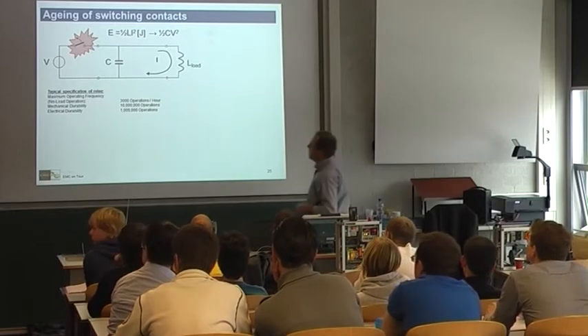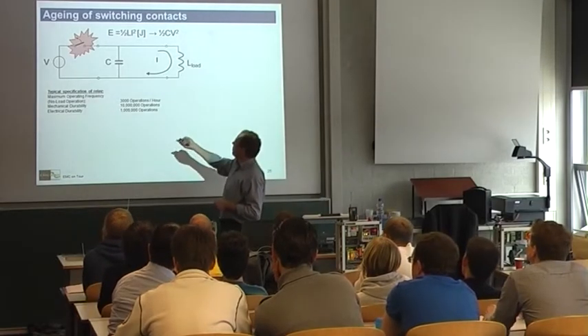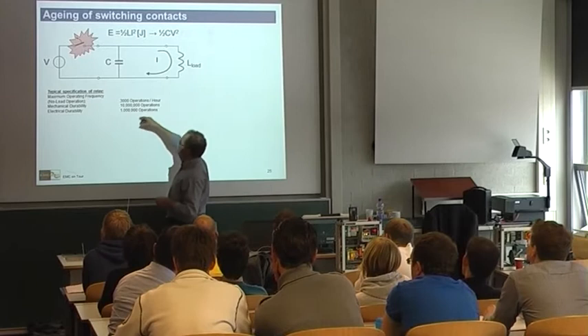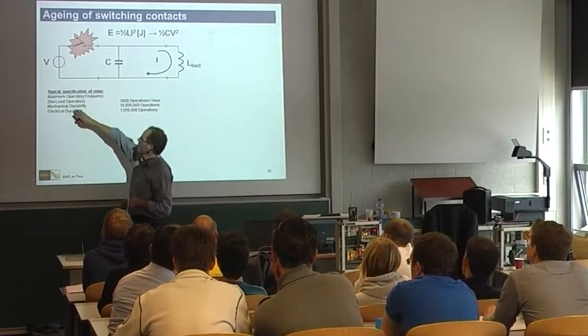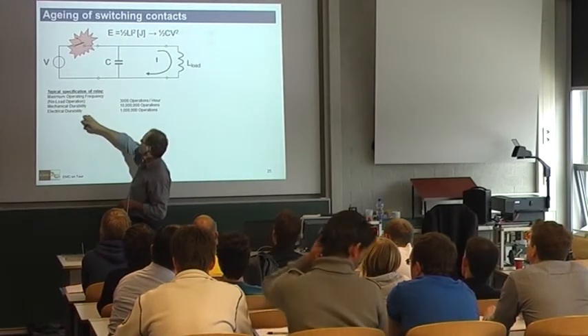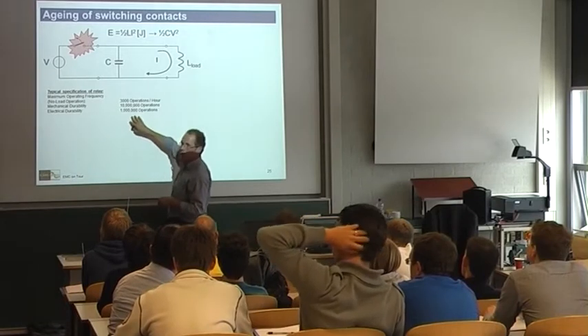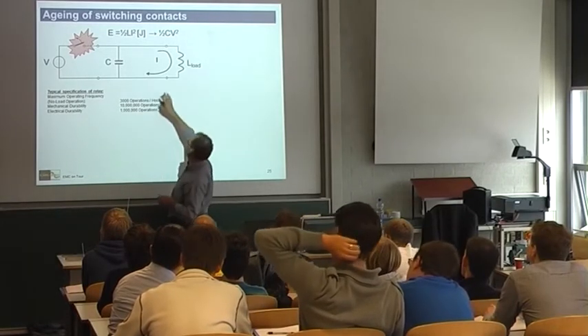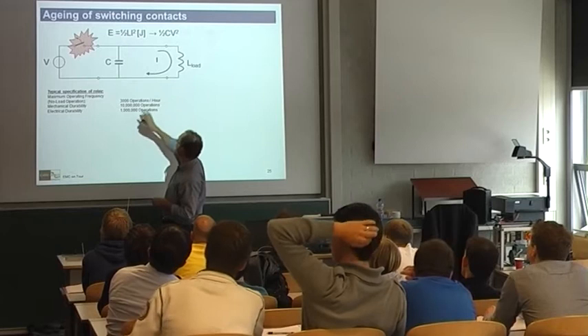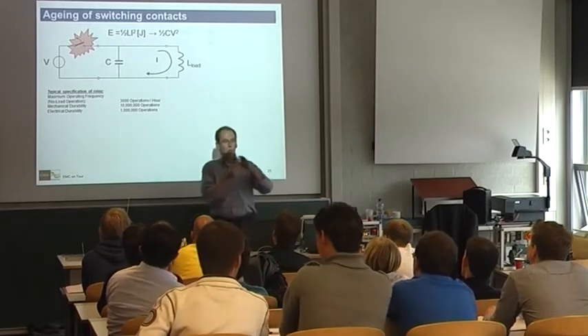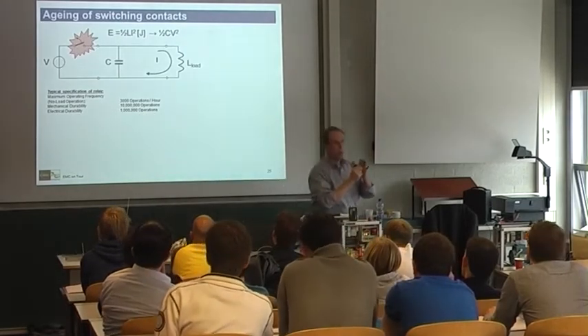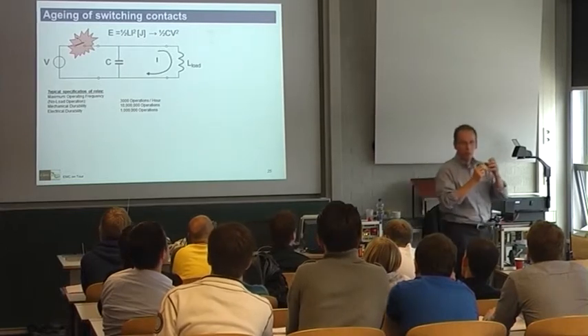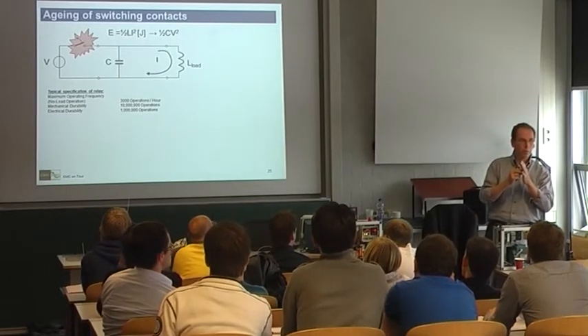When you read the manual, it might say something like 10 million operations should be fine in terms of mechanical durability, but electrical durability is less - maybe 1 million, and that's probably with a resistive load, because with an inductive load the contacts will burn due to the sparking.